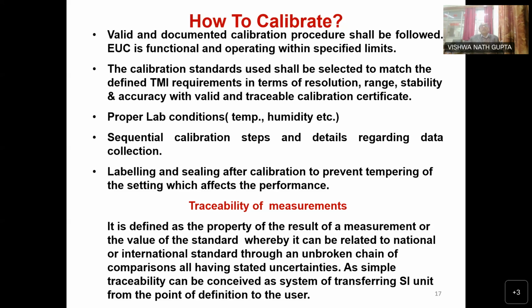So for that, the sequential calibration steps and details regarding data collection: if we have a multimeter, then also one sequential calibration should be there, sir. Like first we touch DC millivolt, then 1 volt, then 100 volt, then 500 volt, 1000 volt, etc. Then current, then resistance, then capacitance, whatever is desired by the firm. After calibration comes labeling and sealing, to prevent tampering with the settings, which affects the performance.